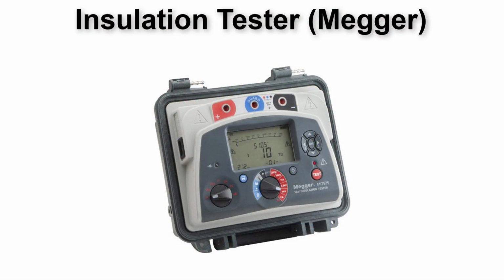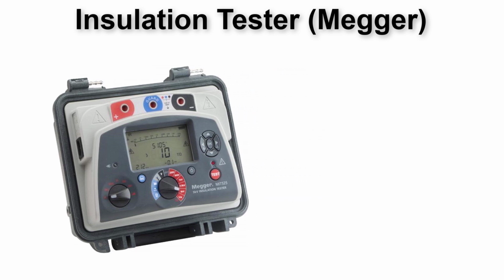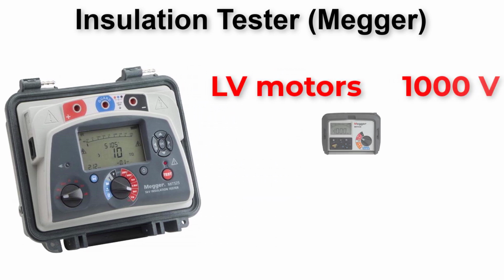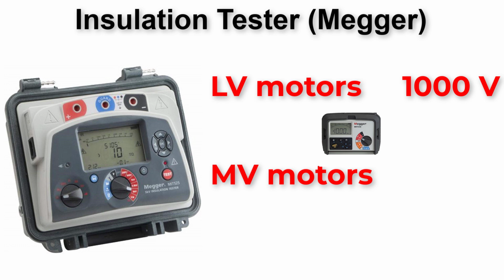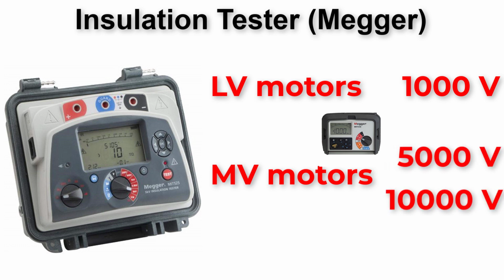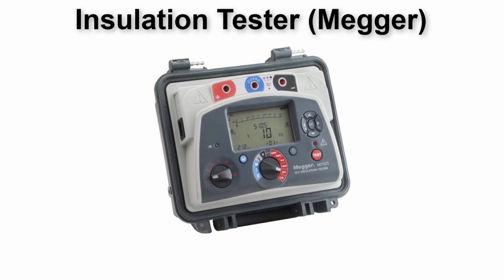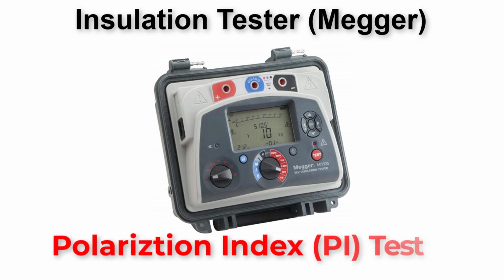We use an insulation tester, or megger, to check the winding insulation of induction motors. For low voltage induction motors, we use a megger with voltage up to 1000 volts. For medium voltage induction motors, we use a megger with voltage up to 5000 volts or 10,000 volts. This medium voltage megger could be used to apply the polarization index test. You can check the video of the PI test in the description down below.